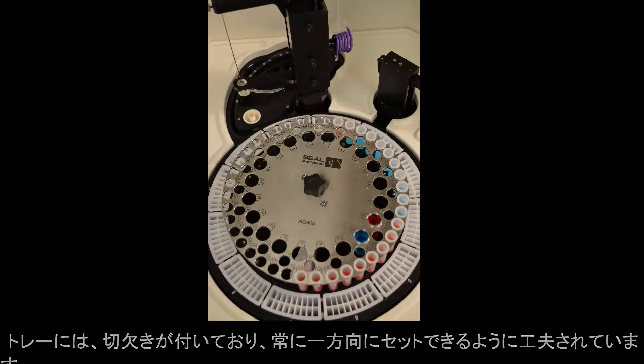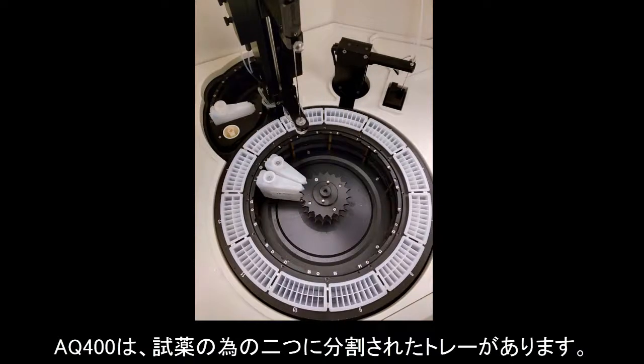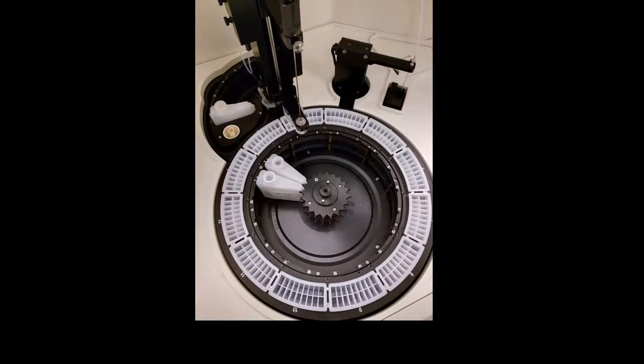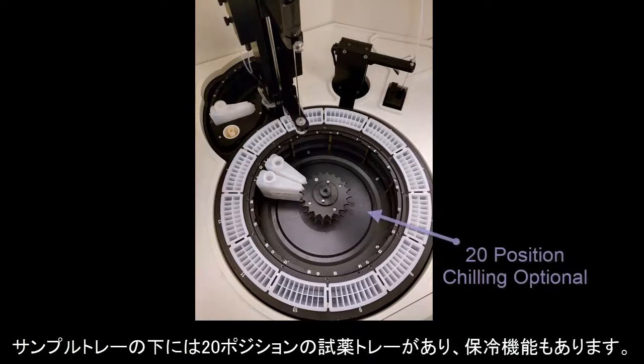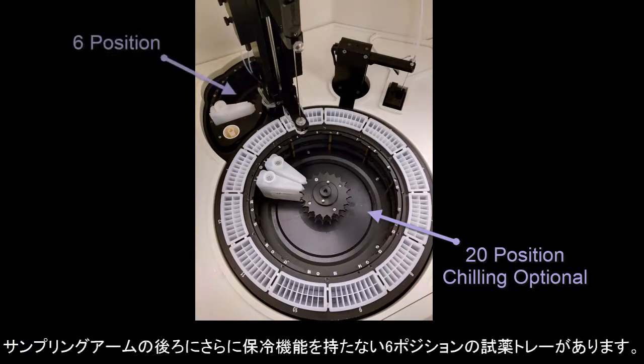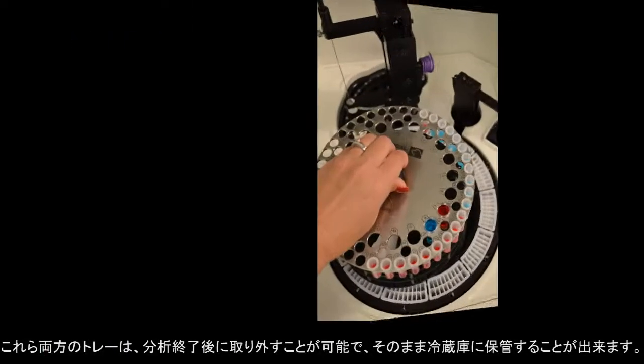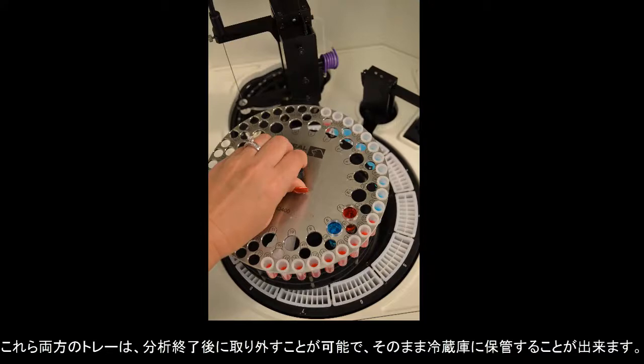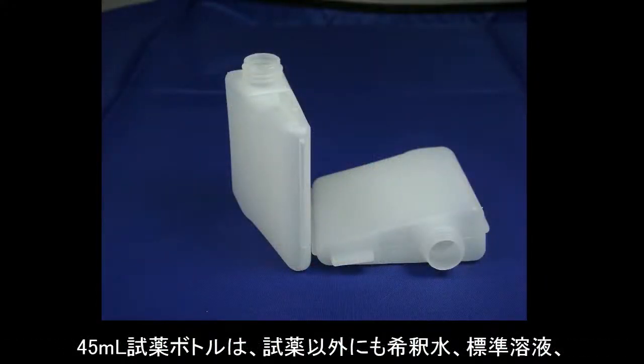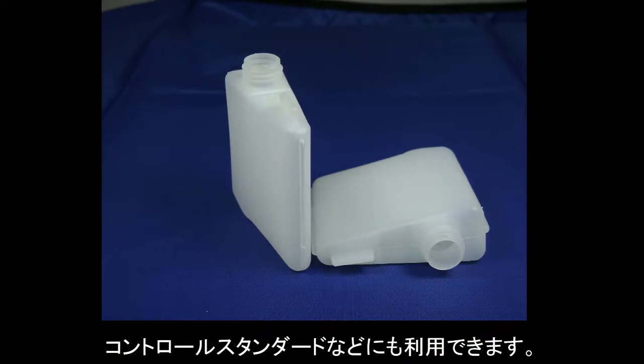The AQ400 is unique as it has two separate tray locations for reagents. Below the sample tray sits a 20-position reagent tray, which has the option to be chilled. Behind the sample arm is another reagent tray that remains unchilled that holds 6 reagents. Both of these trays can be removed at the end of the day and stored in the refrigerator. The 45 milliliter reagent wedges can hold reagents, diluents, calibration standards, and quality control standards.